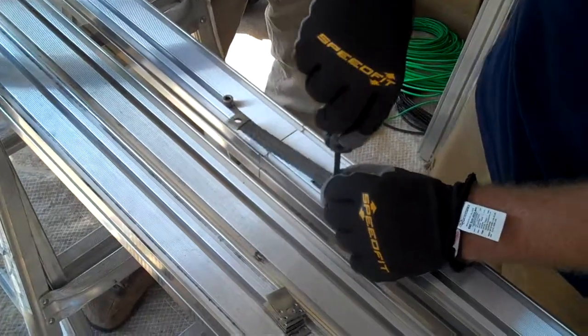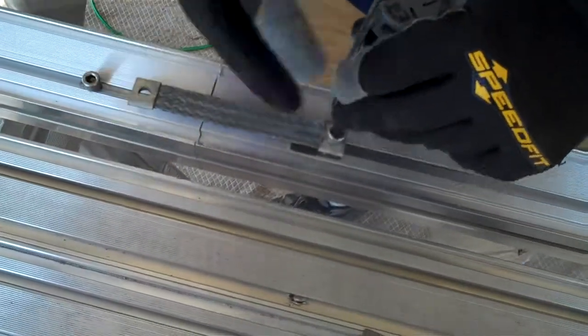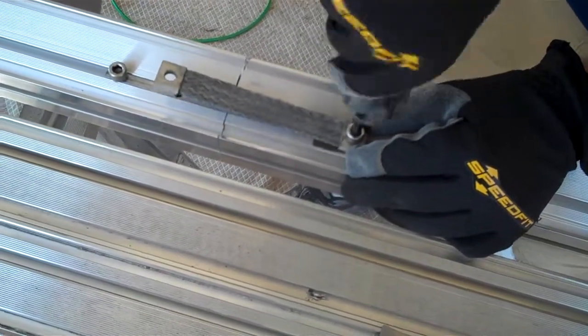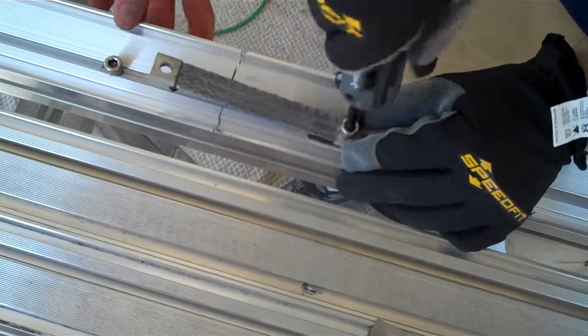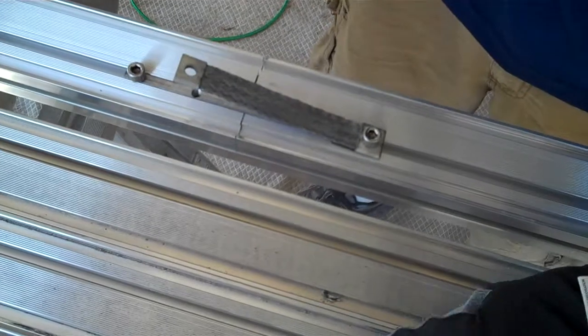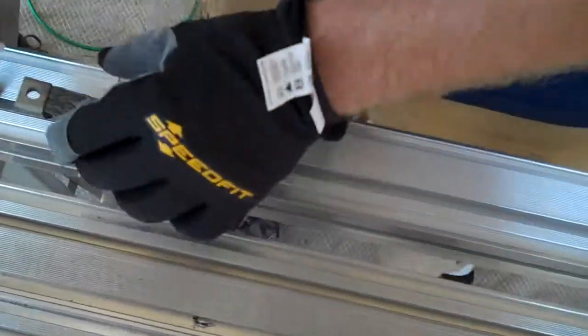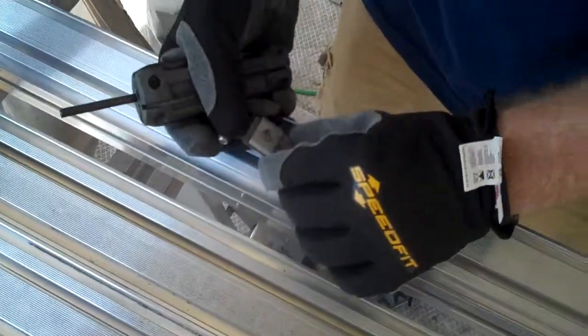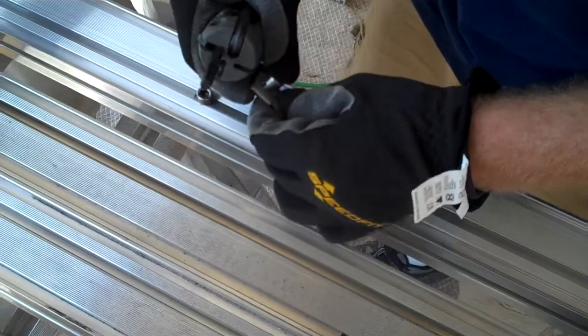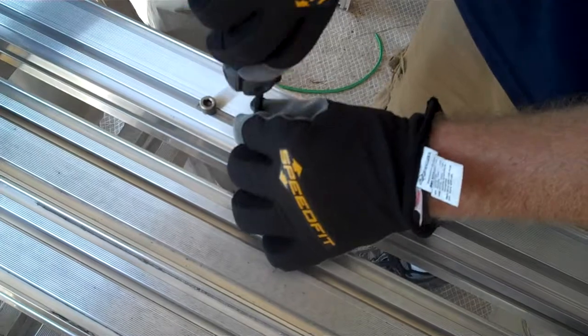What Eric's doing right here is applying an electrical bond or an electrical splice between these two rails. The reason why we're doing this is because it creates one electrically solid piece of equipment, and we can bond this entire piece of rail at one point. That's a Weeb clip — it replaces a conventionally used star washer. When he tightens that down, the four teeth on that Weeb clip are going to bite into the extruded aluminum rail, creating that electrical bond.